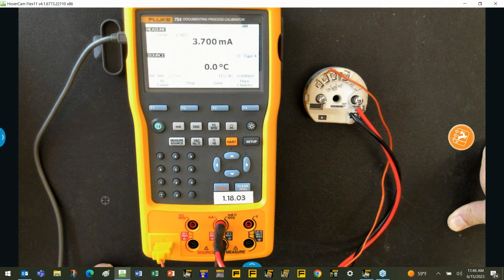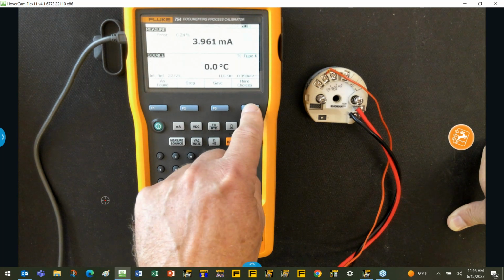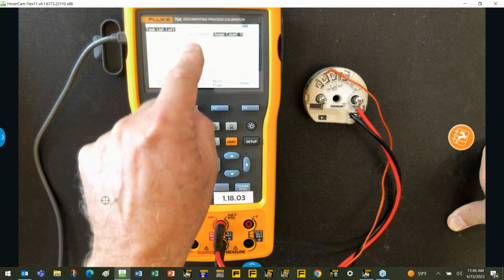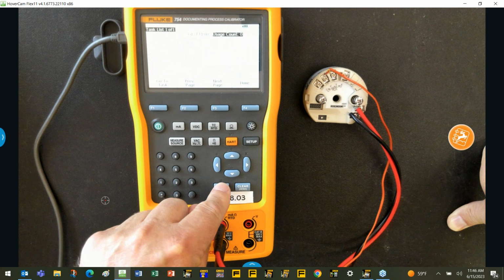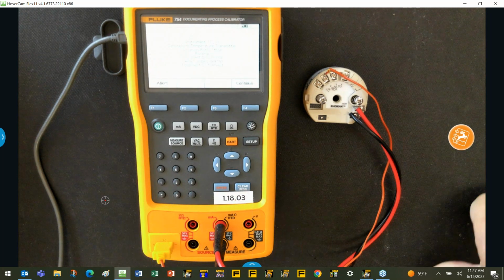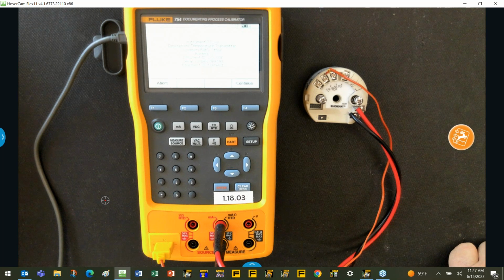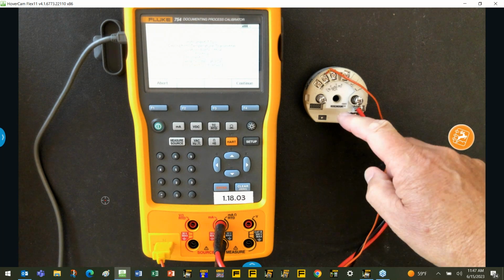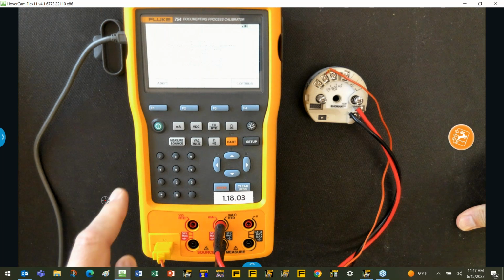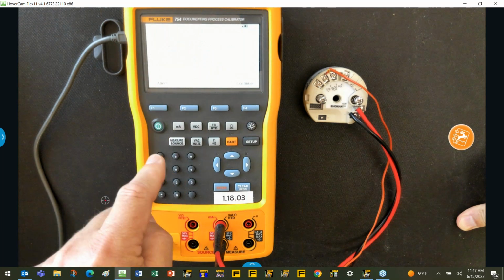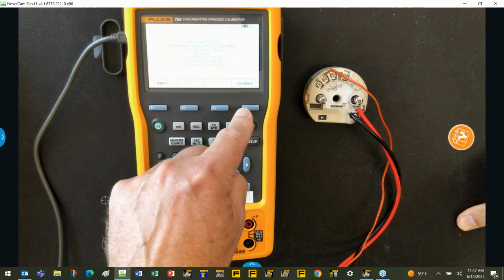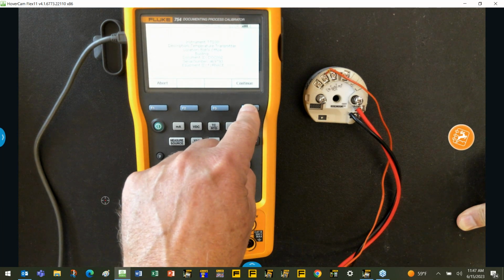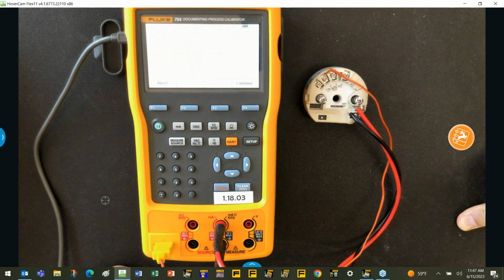Okay, so now we're at the as found screen. Now here's the part where you want to bring up the task that we have downloaded. So we're going to press more choices, go into tasks, and there's that task. We'll enter that. Now it's going to automatically bring up the task into the 754. So the technician now, he's got that TT100 he wants to calibrate, and he's now bringing up the task to run. So you'll see information about the calibration, and then a startup message that Jim was talking about. In this case, I just put verify boxes open, but again, you could put all kinds of things before the technician starts the test.